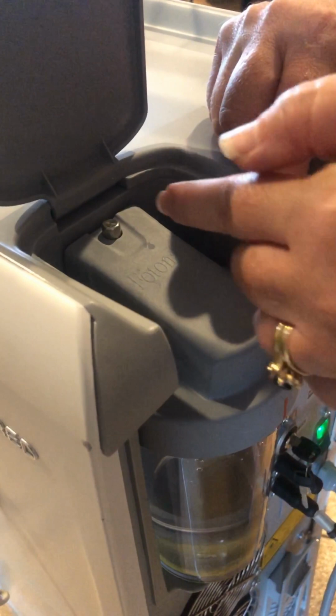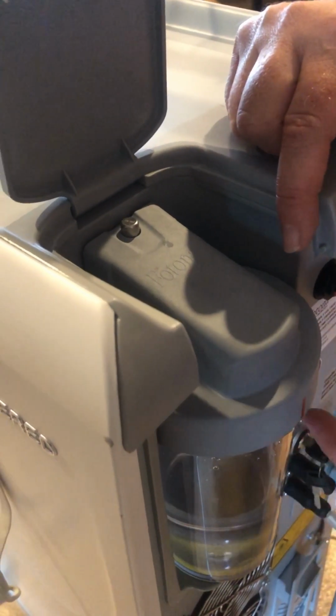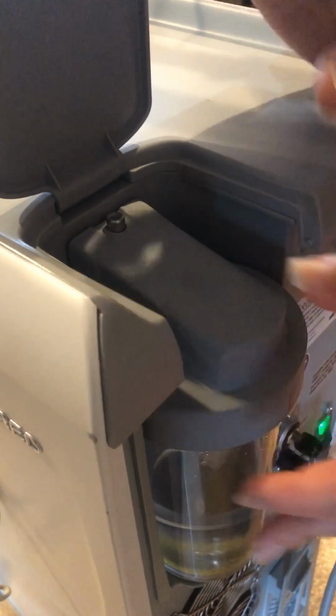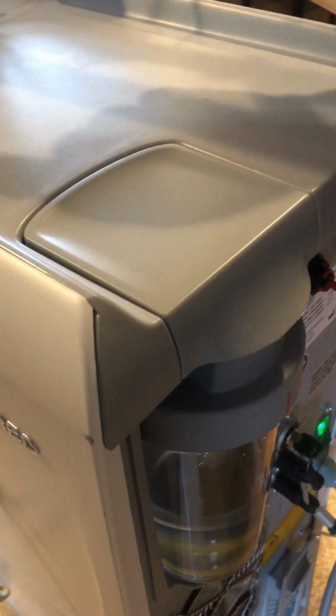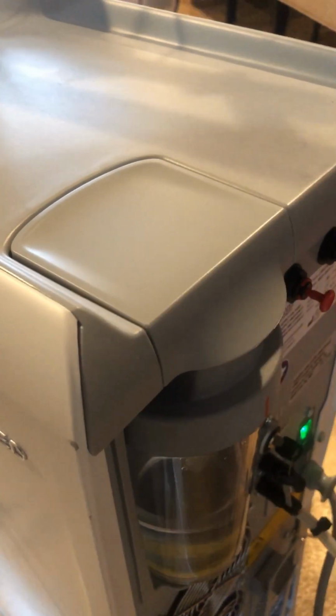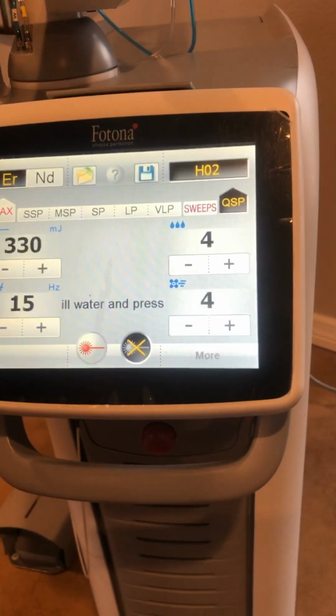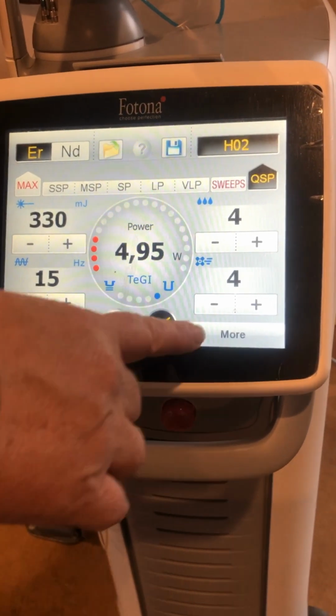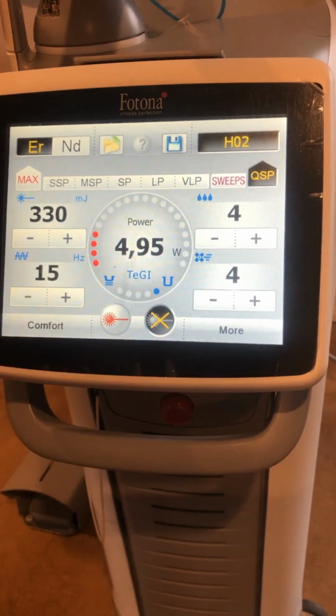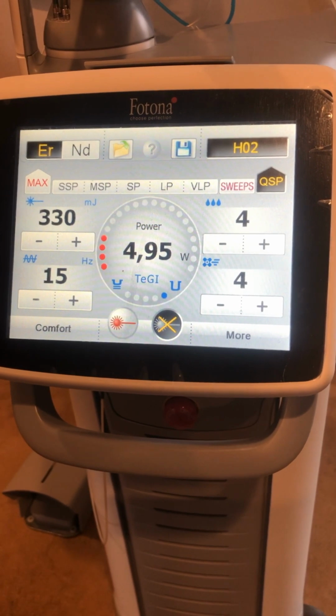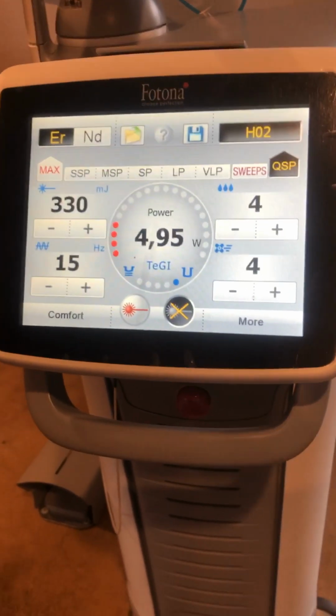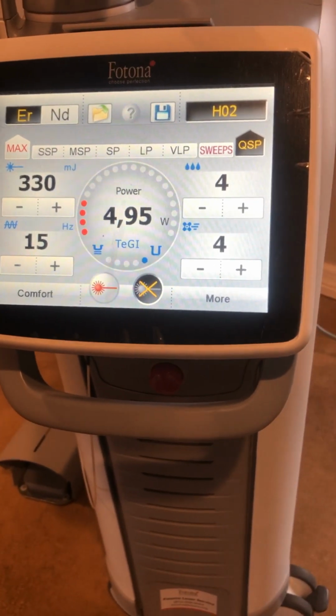There is an actual optic inside there that is reading the amount of water. So if you ever put the water bottle back in and hit OK and it doesn't fill up those blue dots, then that optic is not lined up properly. And then we're just going to come back here and press OK. So all of those things are found in this More button. You're going to go in there a fair amount, whenever you're needing to refill the water or when you're needing to change handpieces or tips.